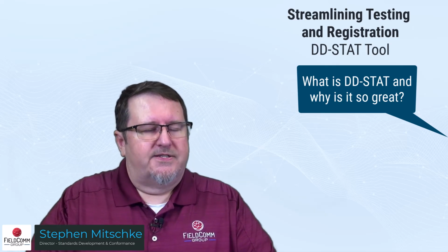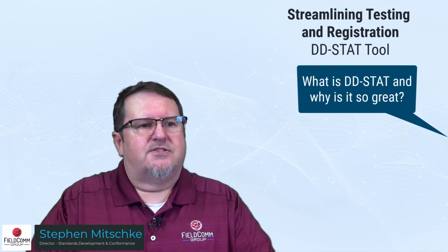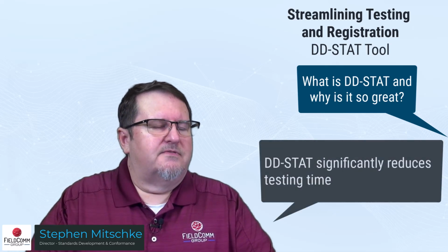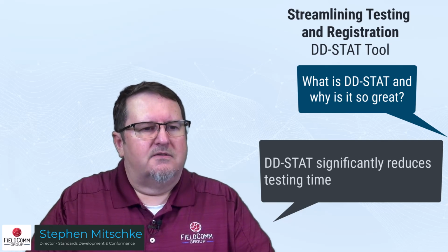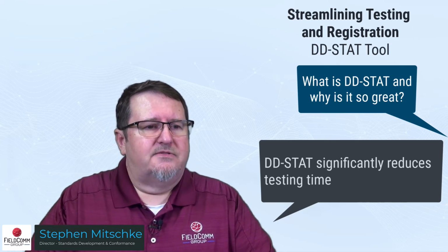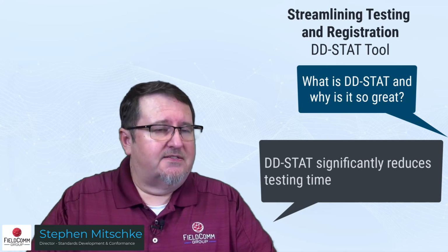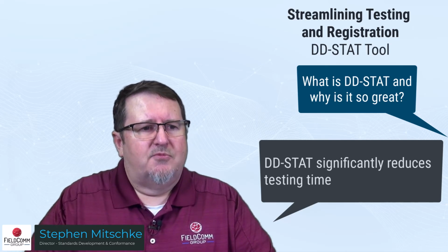So along with the HART test system logs and the current DDs and potentially previous DDs, the static analysis tester will run through a variety of test cases and provide a pass, fail, or sometimes an inconclusive. And that all runs relatively quickly. That's done in minutes. And that allows us to quickly make a first assessment of the DD, give the customers feedback, and more importantly, keep our queue times down.